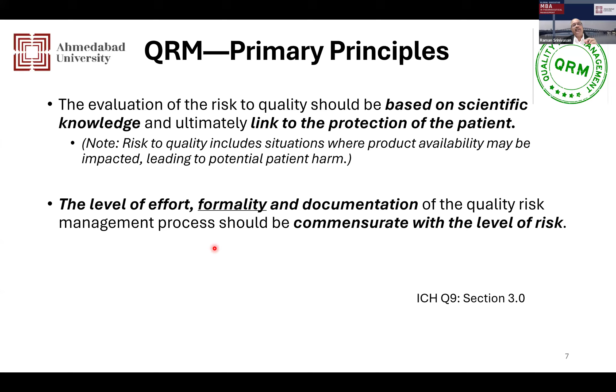Once again, let me use the ICH-Q9 model of the quality risk management process. It has certain steps, and on the right side, you will find the ISO 14971. It also has some steps. If you look closely, there are minor variations in grouping and some wordings, but the backbone of the quality risk management process steps is exactly the same. So for the benefit, in the middle, I'm putting the specific steps that we need to go through. You will comply with both Q9 as well as 14971 requirements.